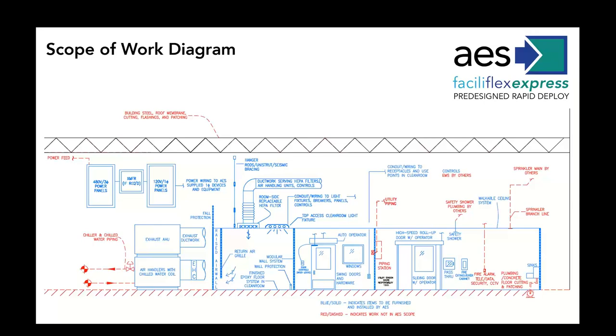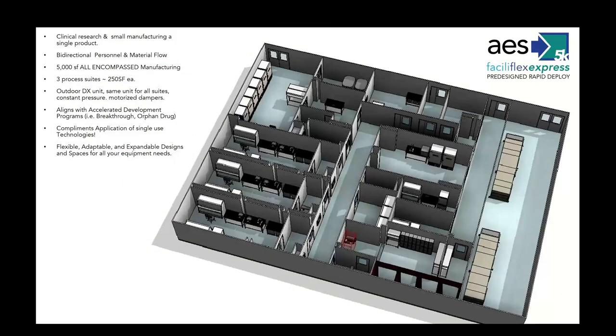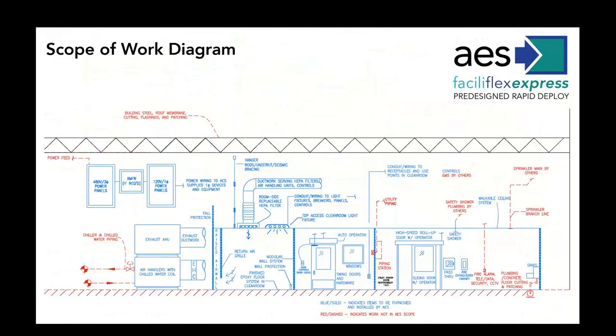Back on that drawing again - you have multiple ducts into your ceiling HEPA modules, don't you? How many, and how much CFM do you normally put in, and how many HEPA modules are there per duct? Because I've seen some designs where you have multiple ducts going into the ceiling.